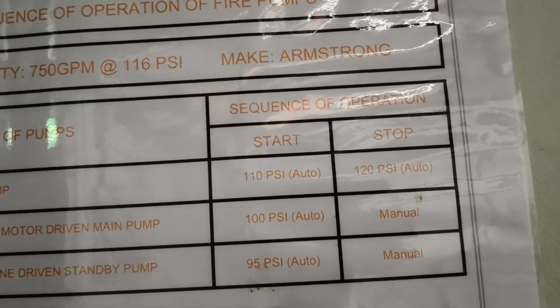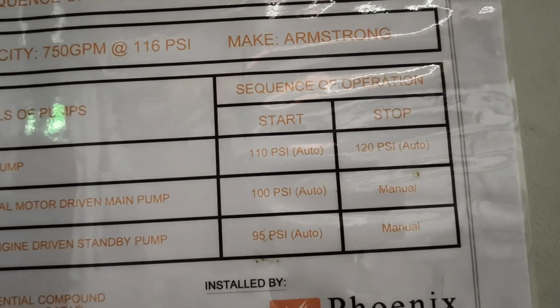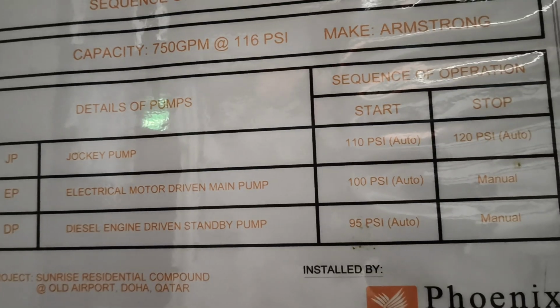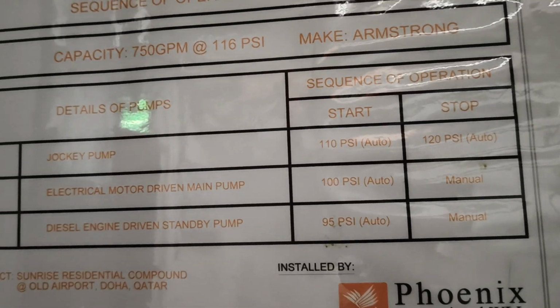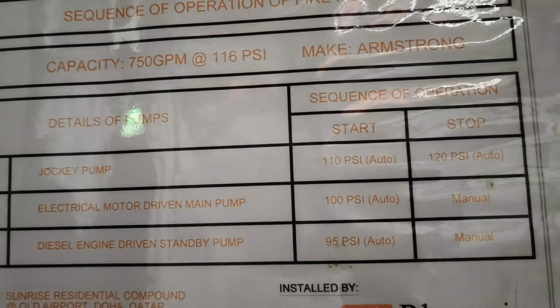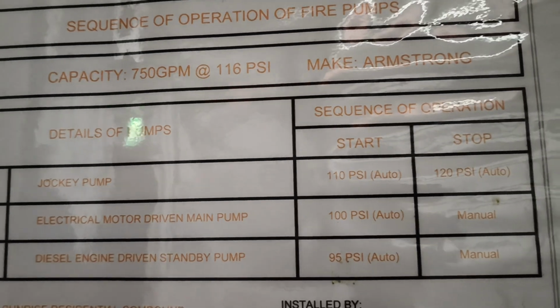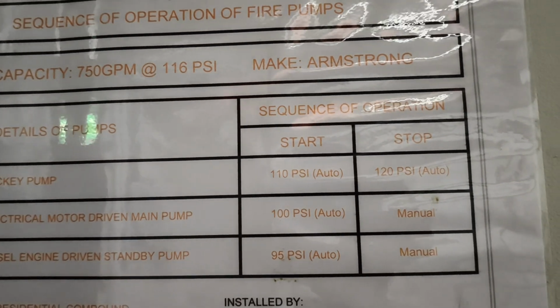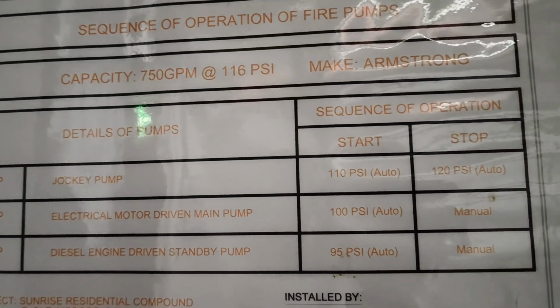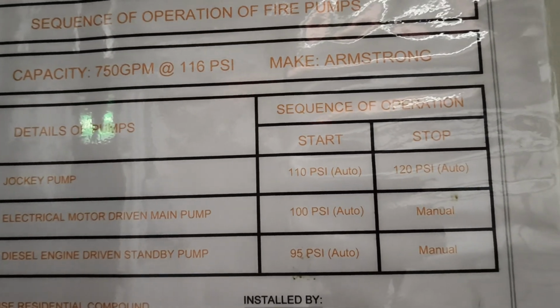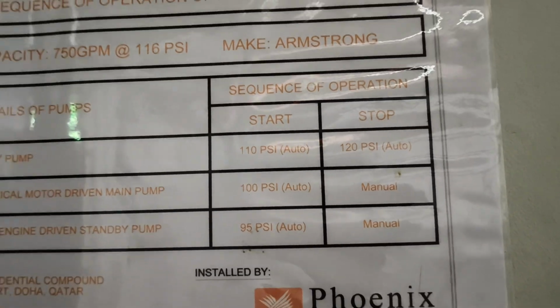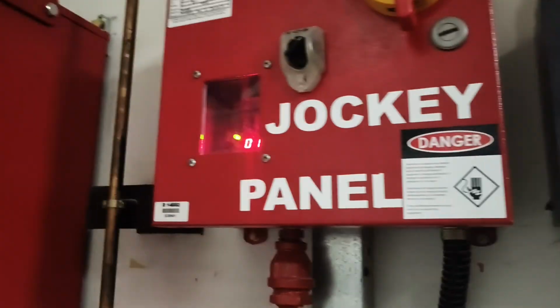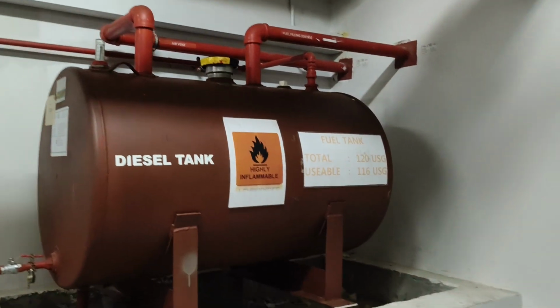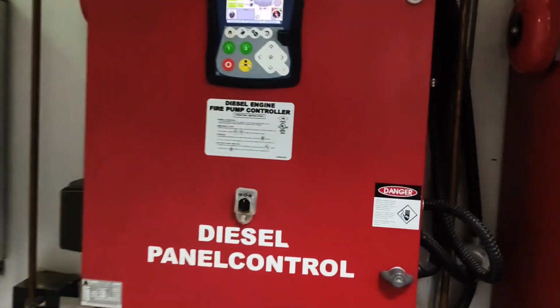The pressure charts that we have: the jockey pump is going to start at 110 psi and stop at 120 psi. The electric motor driven also starts at 100 and manually stops, and the diesel engine driven standby pump starts at 95 psi and manual stop. So the manual stop means you have to put it off by yourself; it is not about the system going off by itself.